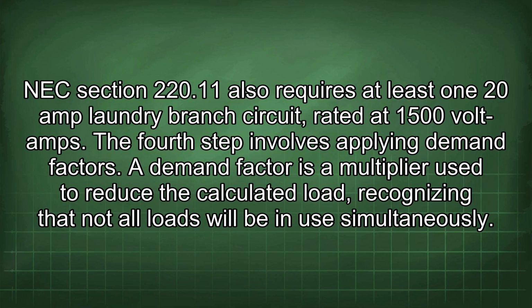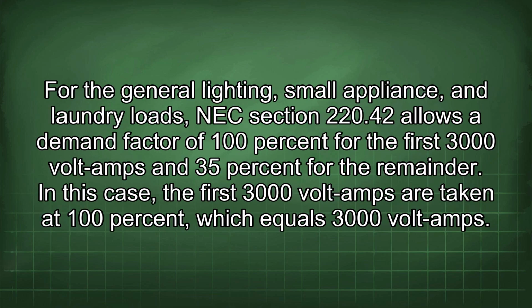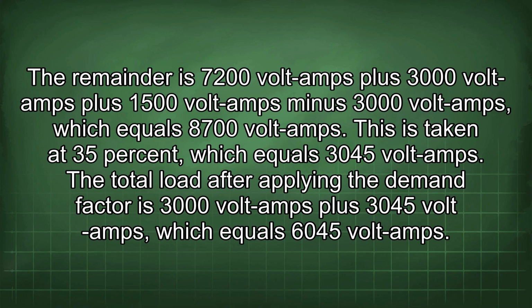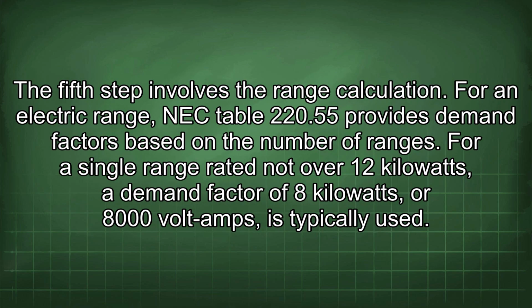The fourth step involves applying demand factors. A demand factor is a multiplier used to reduce the calculated load, recognizing that not all loads will be in use simultaneously. For the general lighting, small appliance, and laundry loads, NEC Section 220.42 allows a demand factor of 100% for the first 3000 volt amps and 35% for the remainder. In this case, the first 3000 volt amps are taken at 100%, which equals 3000 volt amps. The remainder is 7200 volt amps plus 3000 volt amps plus 1500 volt amps minus 3000 volt amps, which equals 8700 volt amps. This is taken at 35%, which equals 3045 volt amps. The total load after applying the demand factor is 3000 volt amps plus 3045 volt amps, which equals 6045 volt amps.